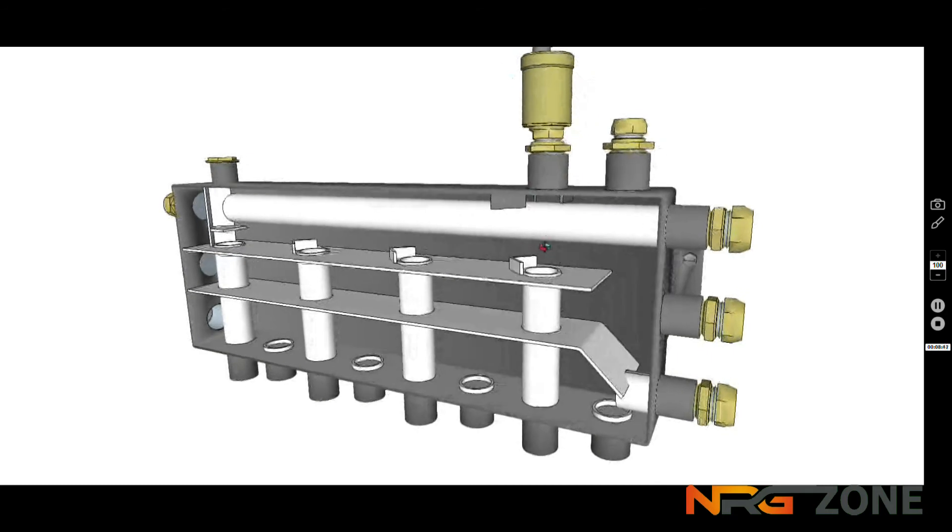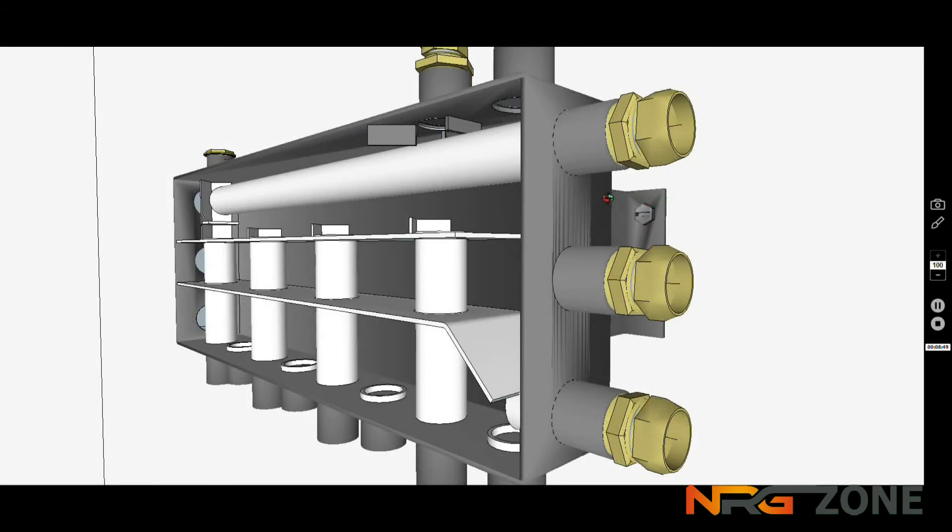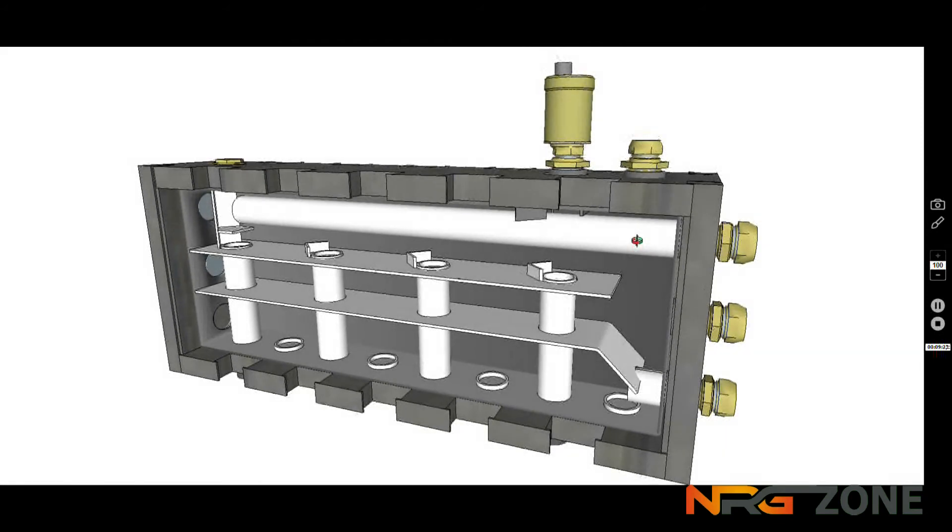To mount the unit, you would remove the insulation, and at the back there are two brackets. You'll note the brackets are mounted about 25 millimeters or an inch from the wall, and insulation passes down in that space, so there's no heat loss from the manifold into the wall. So you mount the unit securely onto the wall. Typically it's best to mount it onto a solid concrete or stone wall, but if you have to mount it onto timber, it's a good idea to put something like insertion rubber, or some kind of rubber mask behind the thing, so that it stops any slight vibration that might go through from pipework or from the pumps operating. When the unit is mounted, you're ready to start piping your system. It's a very good idea to make a diagram before you start, and the logic of this system would make it very simple for a diagram to be created.